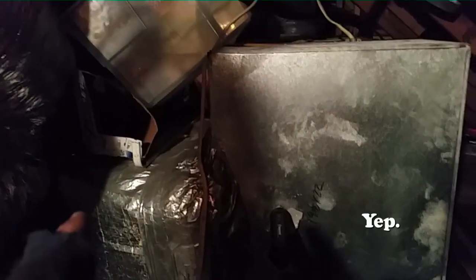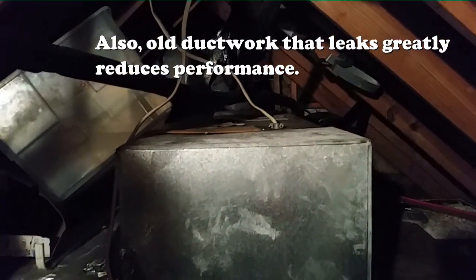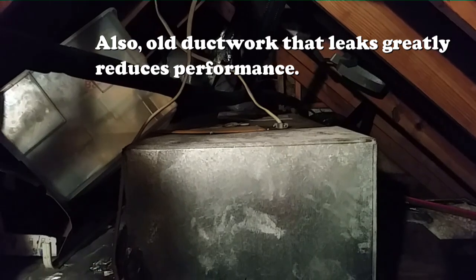Supply ductwork runs down, and looks like it runs up over there. It's a weaving trail of crap. And the attic, I'm sure, is hot. So we're going to take these two temperature measurements and temperature spread, check the machine again, because I think it's going to be fine. And then we'll put the Fieldpiece on the farthest outlet to see how much it warms up between here and its destination at the grill, because sometimes our warmer attics can cause problems as far as losing your cooling before it gets to the actual living space. So we'll see if that's one of the causes of this problem.